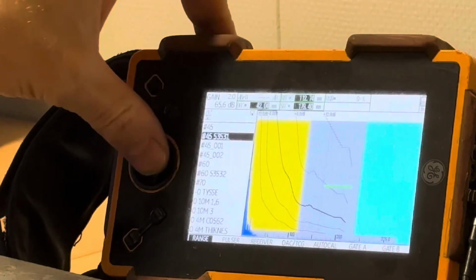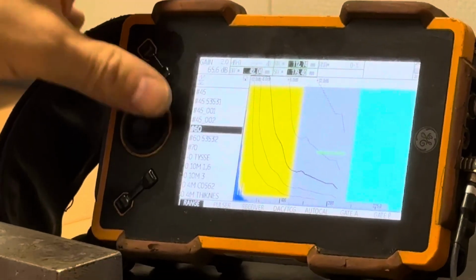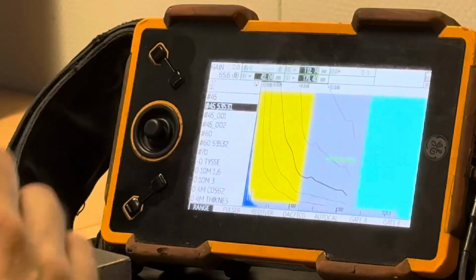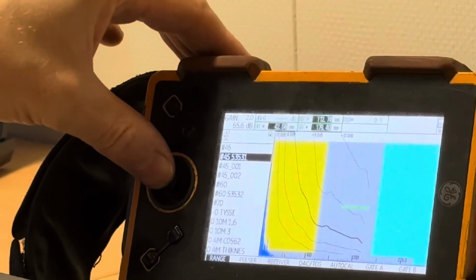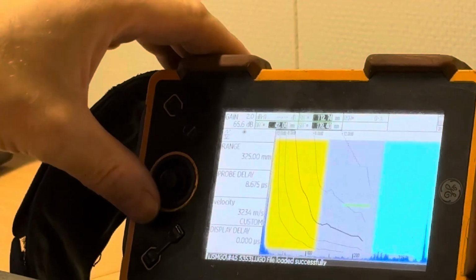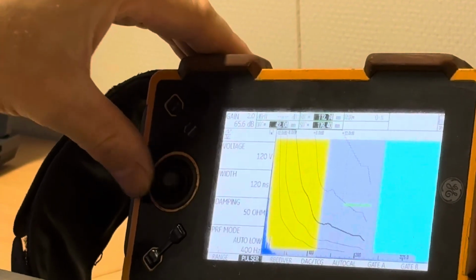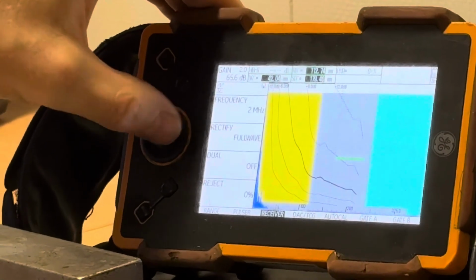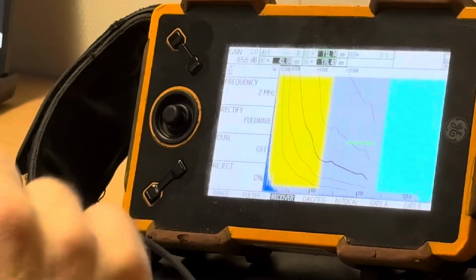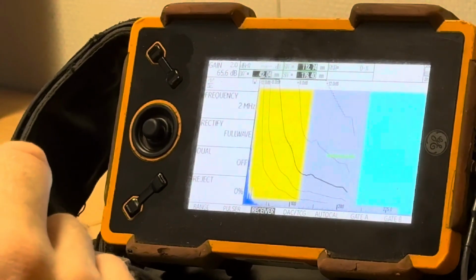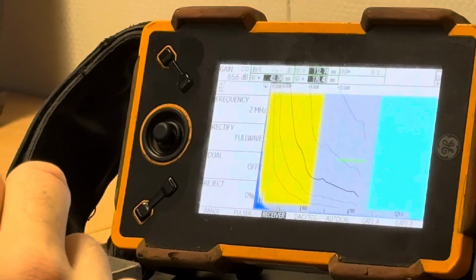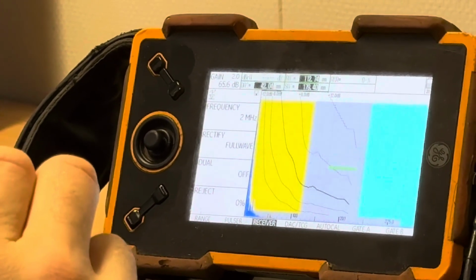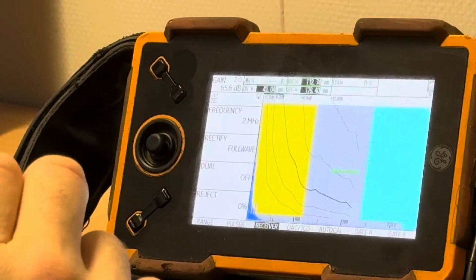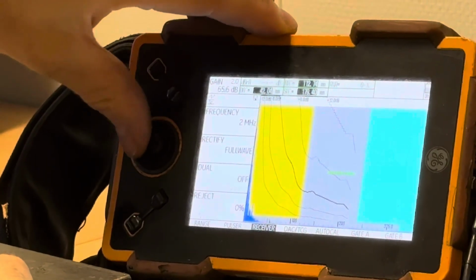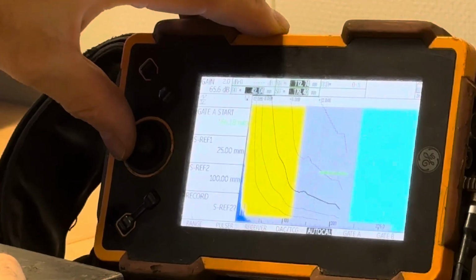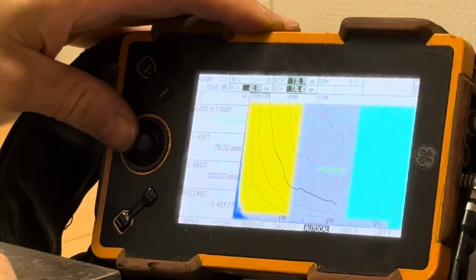And we call up the probe that we need. It may already be calibrated, so we can easily find it here. Usually, it is recorded by serial number and by angle. We select 45 degrees. The first thing we check is to make sure it is set to 2 MHz. This probe uses 2 MHz for thick metals. For large thicknesses, that is to say, when dealing with a significantly large probe, we utilize specific settings. Conversely, for small thicknesses, we consistently employ a 4 MHz frequency.